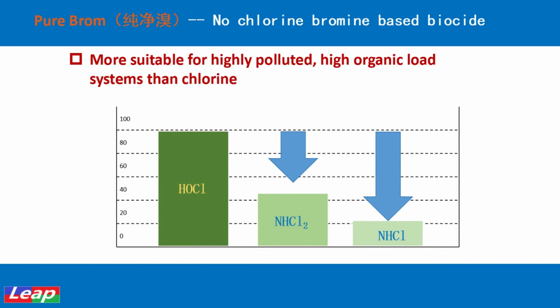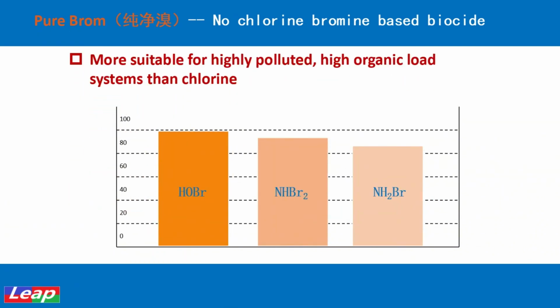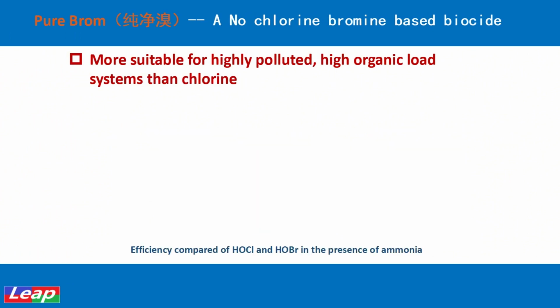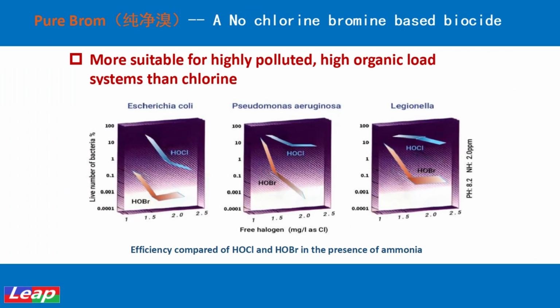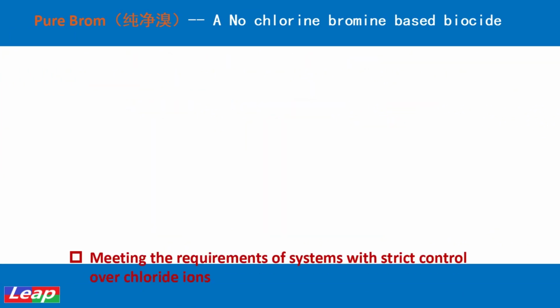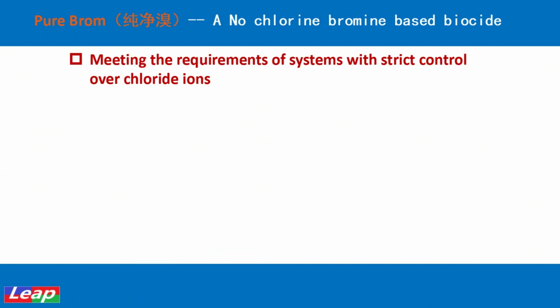In highly polluted, high organic load systems, organic materials react with hypochlorous acid to form chloramines. The sterilizing efficiency of chloramines is only 1/30th to 1/80th that of hypochlorous acid, and they are not easily degraded, posing significant environmental hazards. The hypobromous acid produced by the hydrolysis of Pure Brom will similarly react with organic materials to form bromamines. Bromamines themselves are excellent disinfectants, with sterilizing capabilities almost equivalent to hypobromous acid. Furthermore, after exerting their disinfecting action, bromamines rapidly degrade in water, without leaving behind residues that could harm the environment, meeting the requirements of systems with strict control over chloride ions.